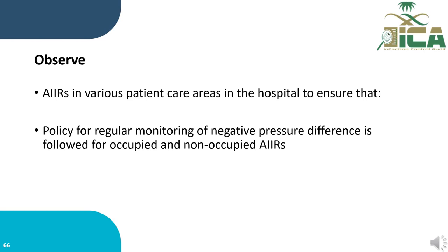And here we want to mention that the pressure from the monitoring device installed at the entrance of the airborne infection isolation room should be recorded daily in the logbook designated for this purpose by the responsible nursing staff in the department. You will check this documentation and you can see if there is regular monitoring of the negative pressure difference.